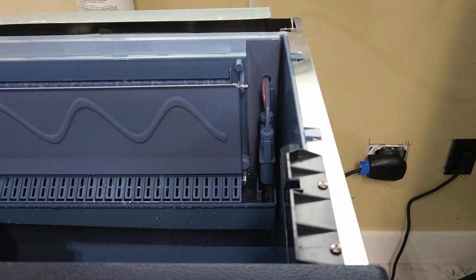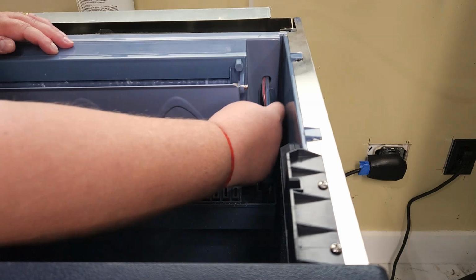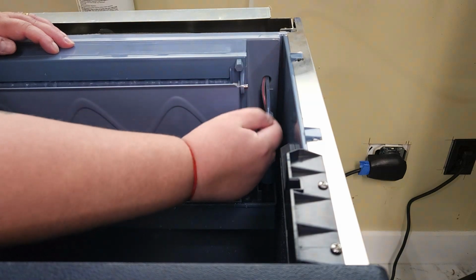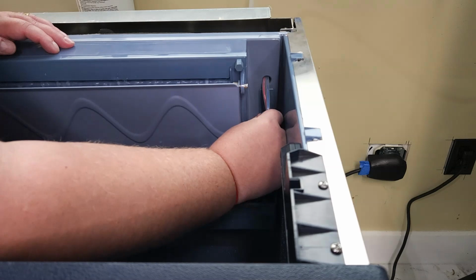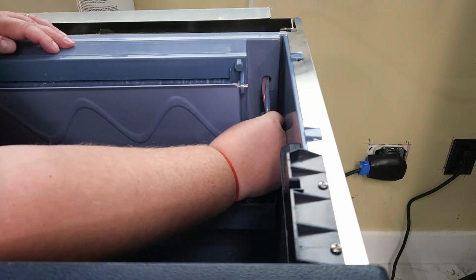The probes on the ice maker are on the right side of the ice plate. The probe we need to adjust is the harvest probe. This probe is characterized by having a red wire going to the top of it. To adjust the probe, we will need to either raise or lower it. Raising the probe will make the bridge of ice between the cubes thinner. Lowering the probe will make the bridge of ice between the cubes thicker.